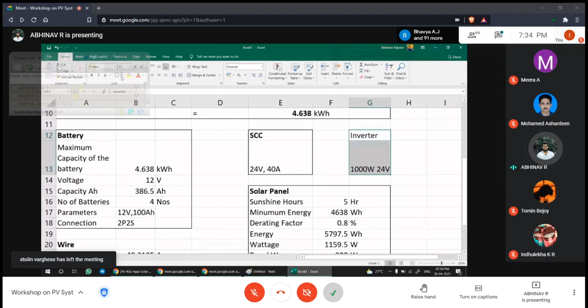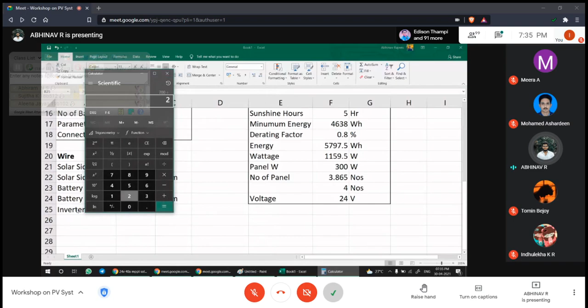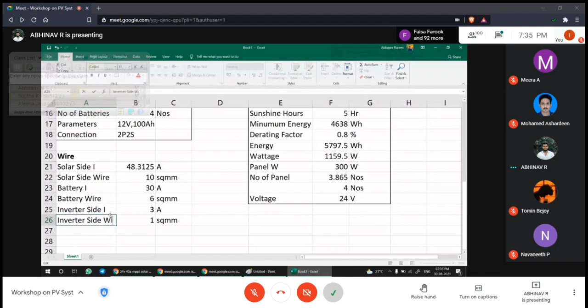So coming to the inverter side current. It is converted to AC, right? So now the 700 watts is only going through 230 volt, 3 amperes only. So you can go for a 1 square mm wire. 3 amperes, 1 square mm wire. So this is regarding the wire. Yeah, this is the calculation.